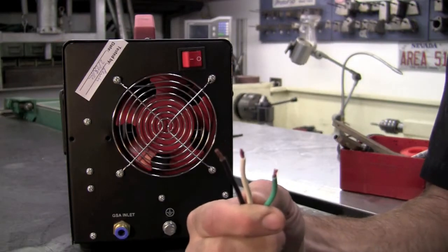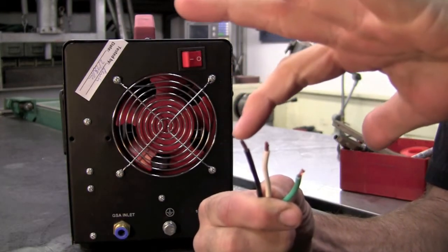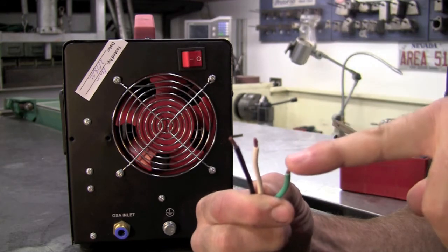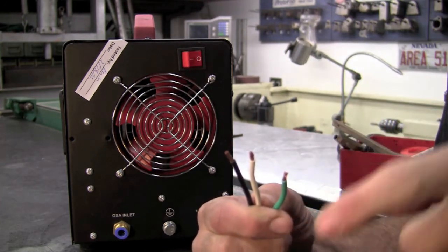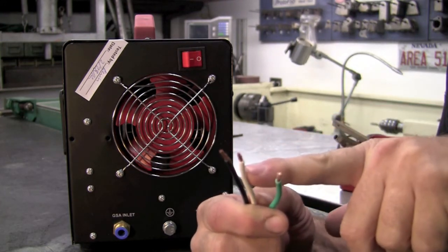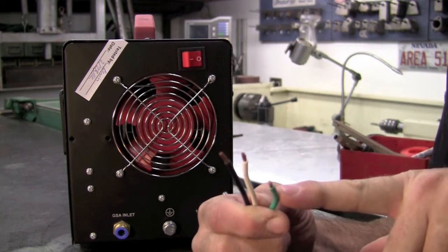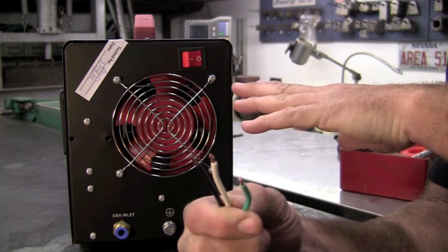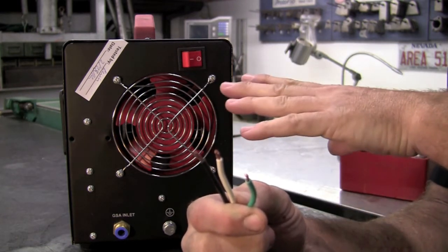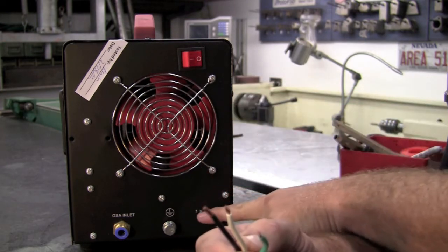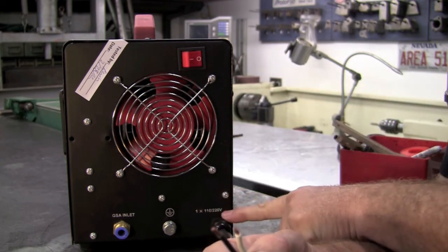For wiring in the 110 mode, black will be your hot, white will be your neutral, and green will be your ground. In the 220 mode, black and white will be your hots, green will be your ground. The machine automatically knows how to switch over inside between the dual voltages. You note on the back of the machine, it does say that it is dual voltage.